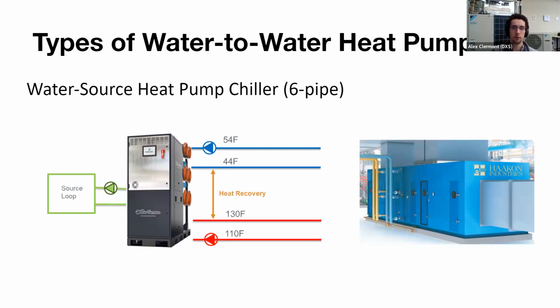And if you're doing a geothermal system, the major competing systems or options are straight water source heat pumps, where your geothermal loop runs through your entire building. If it's residential, you put a water source heat pump in each suite, or if it's a school, you put it in every classroom. Or you could also do water source VRF, where you're running refrigerant piping throughout your building to deliver heating or cooling, which is a bit of a more expensive option, but it's more efficient.